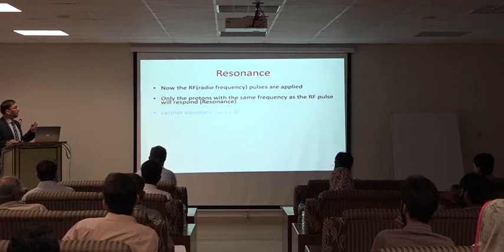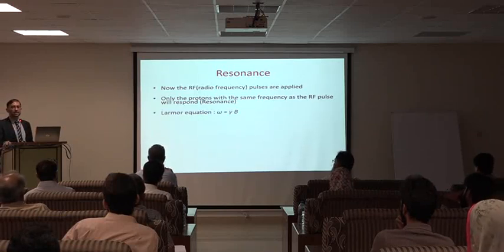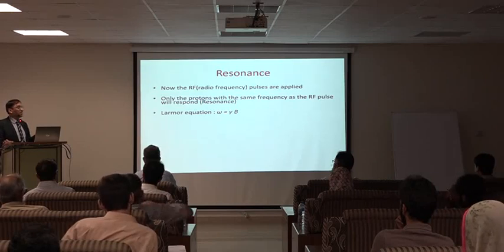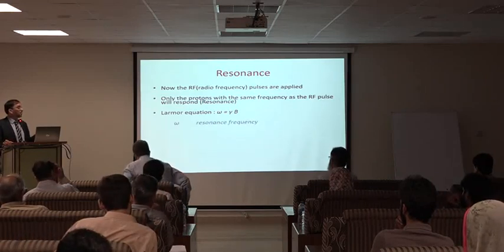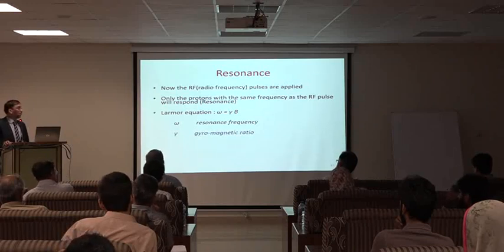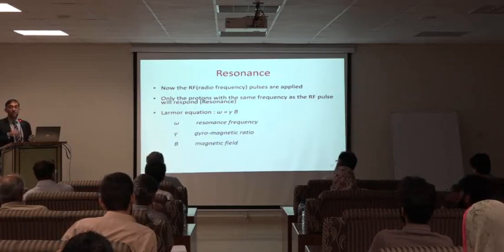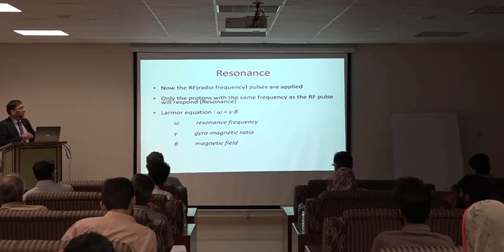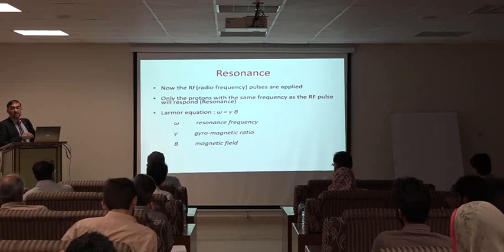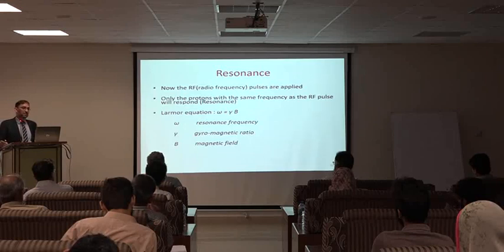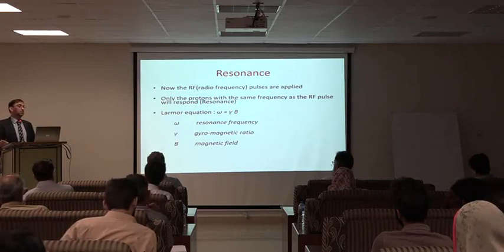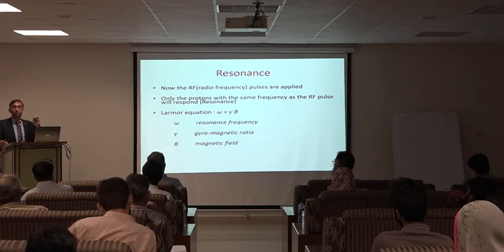And by the way, how is that frequency calculated? It's calculated from the Larmor equation, omega equals gamma B, where omega is the resonance frequency, gamma is the gyromagnetic ratio, and B is the magnetic field. So what does it tell you? If it's a 1.5 Tesla scanner, B is 1.5, and omega will be different. If you increase the strength, a 3 Tesla scanner, omega will be a different number. So when you are designing the transmitter coils or the receiver coils, you have to be careful about which frequency you are talking about, and which particular scanner this is designed for.